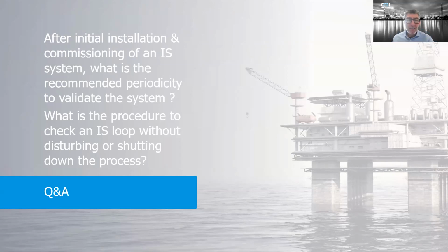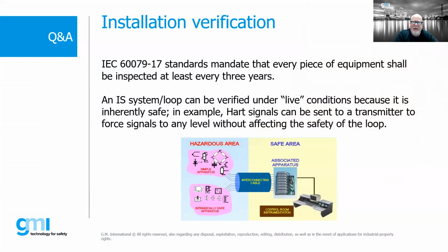What about commissioning, after installation commissioning of an IS system? There is a recommended periodicity to validate the system. How often do I need to check? Yeah, so the 17 standard states that every piece of EX equipment shall be inspected at least once every 3 years. So 3 years is the number. There are specific installations where you would say things like portable equipment no more than a year. There are some other ones that are spelled out.